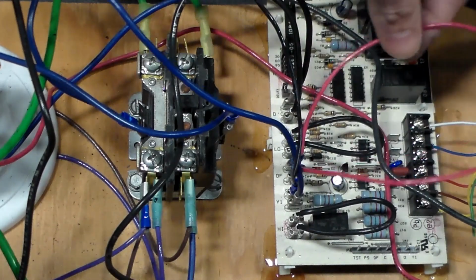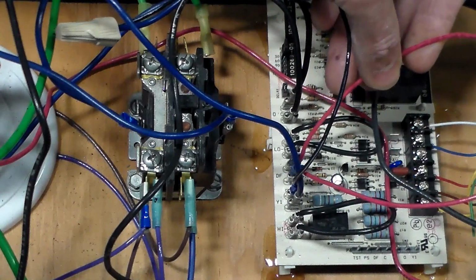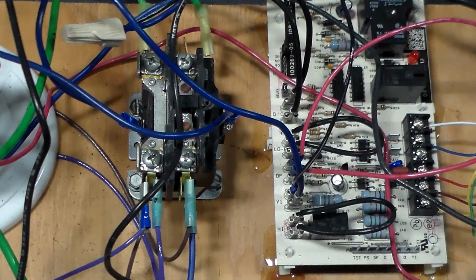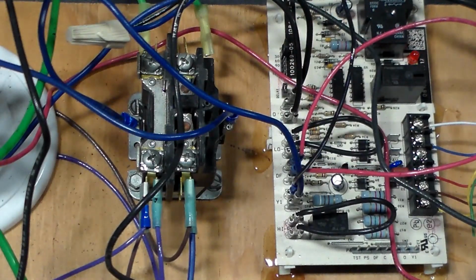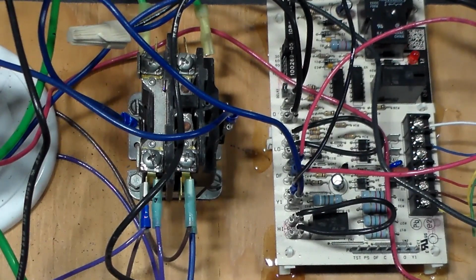Now DF is your defrost sensor. And again, I have it jumped out because that way I can run it in defrost and make it do all the things it's supposed to do, and it'll respond appropriately. We'll talk about testing in a little bit. But that would be where your defrost termination sensor would go. And that'll be a 2-wire thing, usually a snap disc or a thermistor of some type that would plug in that defrost sensor to tell the board that there's a need for defrost. So the board is going to try to defrost every so often if there's a need. If there's not a need, it'll reset its timer. It'll try again after another period if there's a need. And then at the end of defrosting, that same sensor is going to tell the board, hey, I don't need to defrost anymore. You can go back into regular heat mode now. So at DF, that's very important. That's where your defrost sensor would plug in.